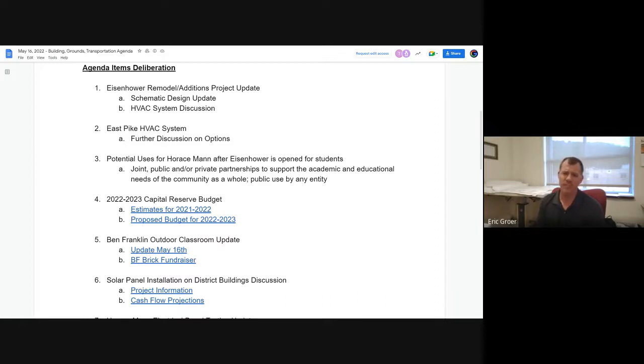There's just a lot more pieces of equipment to deal with, compressors above the roof. Also, putting compressors in the classrooms does present a concern for noise. And this system does not have active dehumidification control. What I mean by that is in any air conditioning system, dehumidification is a byproduct of air conditioning, but with water source heat pumps, you can't actively go into a dehumidification mode. So if you're air conditioning, you will dehumidify. But in milder climates, 70, 75 degrees, when it's humid outside, you can't really dehumidify without subcooling. So that's a concern. Estimated first cost is about $3.8 million with this option. And the estimated energy costs per year are the lowest of the 5 options at $28,928 a year.